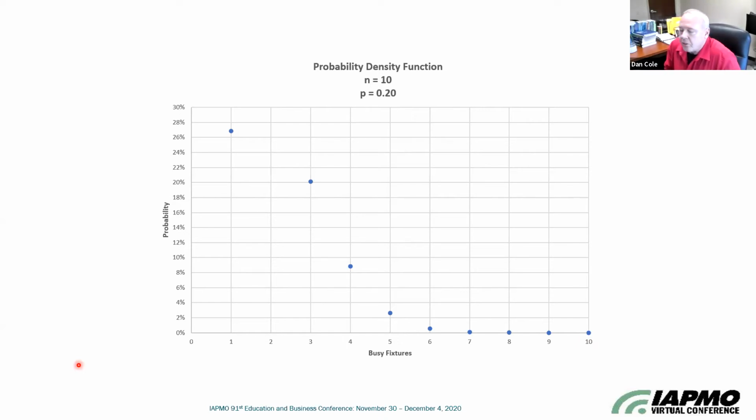And the sample size is too small to determine an accurate 99th percentile. Another method was needed when the fixture count is low. So this is another fault of the Hunter method. His method is good when there's a large number of plumbing fixtures for large buildings.